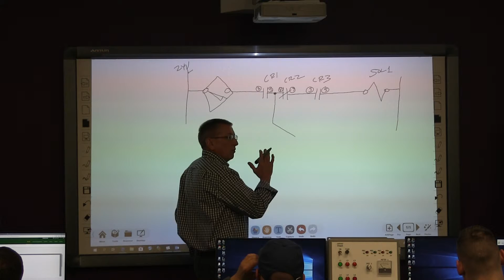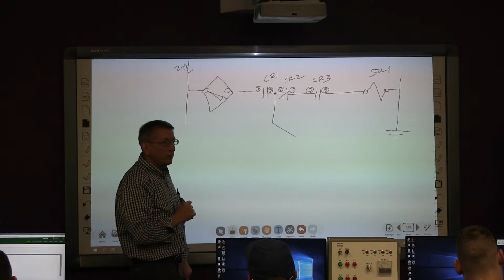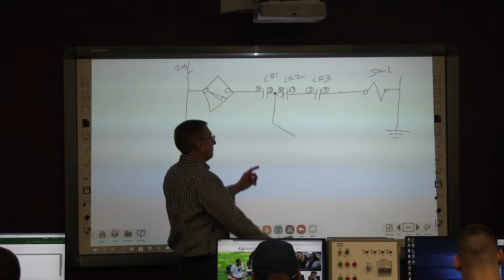Unless you know the machine really well. So we start measuring - when we start measuring, what do you always reference? Always, always reference ground or common. Because what happens, and you've seen these guys do it, they'll take a meter and just touch a point - that tells you nothing, you have no reference. So you have to start at a reference and work your way from there. Always use a reference or a ground, and make sure you've got a good ground that you're using.